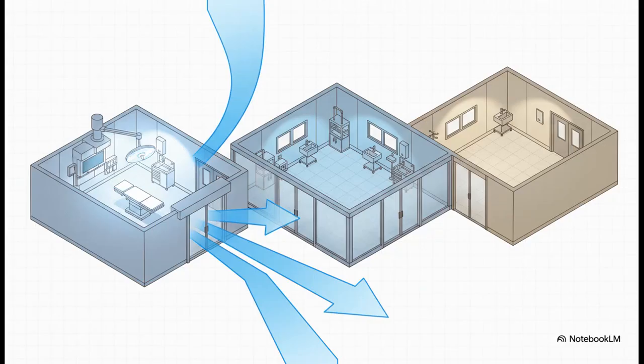To add another layer of protection, the physical airflow is heavily engineered. Ventilation systems are calibrated so that air pressure pushes outward from the cleanest area. It flows from the sterile zone out to the substerile zone and finally out to the clean zone. So if a door does happen to open, the clean air pushes outward, making sure no contaminated air from the hallways ever blows into the surgical space.